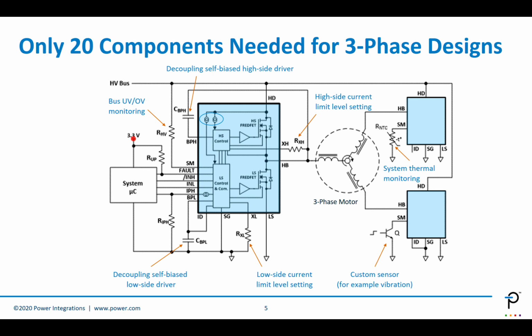The differences are two. One is there is only one wire, not 2. And secondly, the slave, in this case the BridgeSwitch, can initiate the communication. The driver software which is required to implement this capability on the microcontroller is very small, around 2 kilobytes flash and 30-40 bytes RAM. The third feature of the SM pin is to attach a custom sensor, for example a vibration sensor, with the same trigger-based functionality as we described for the external NTC.